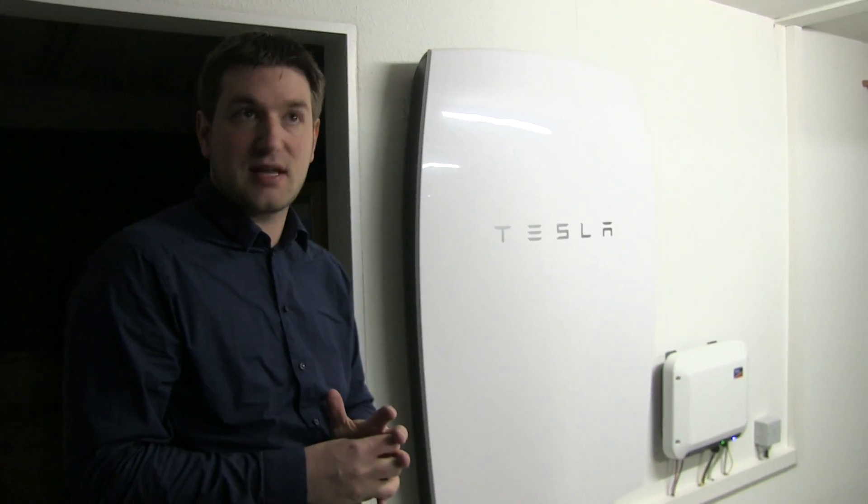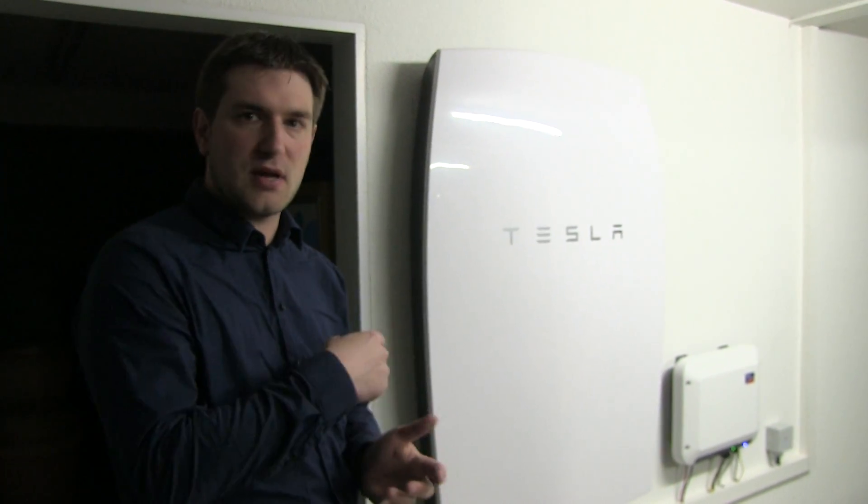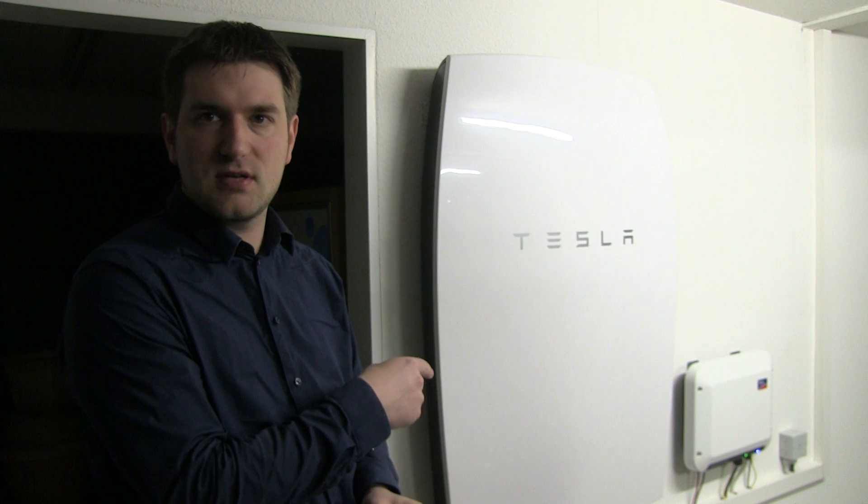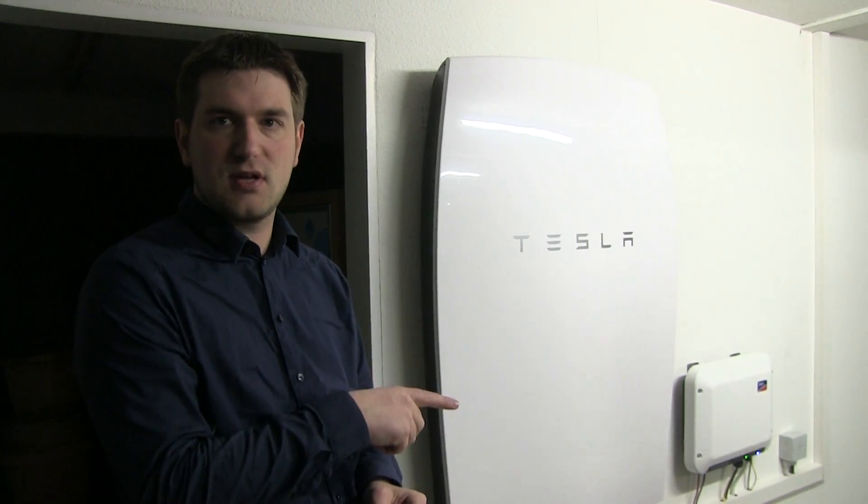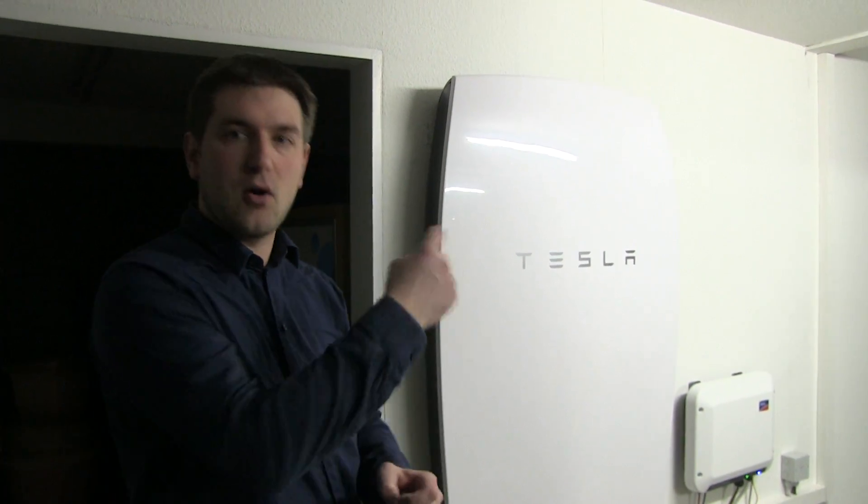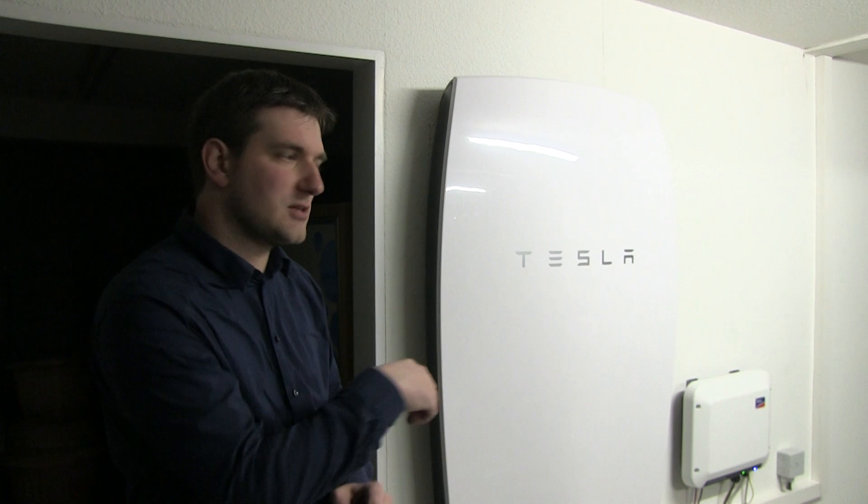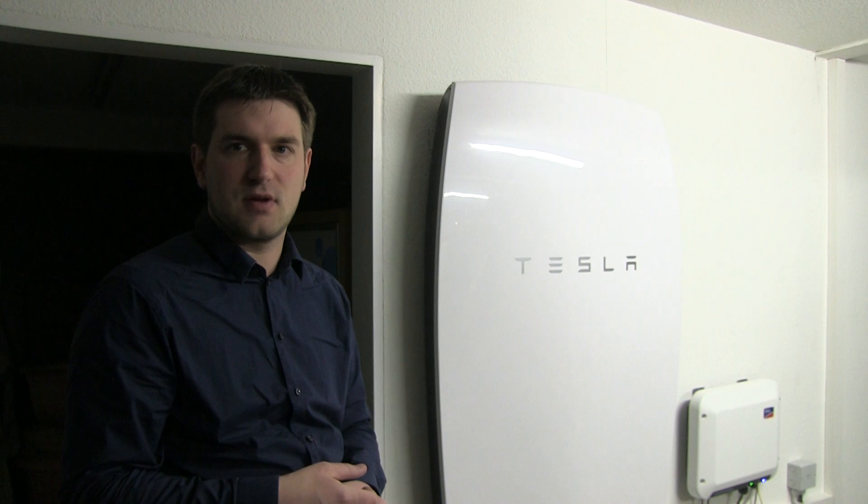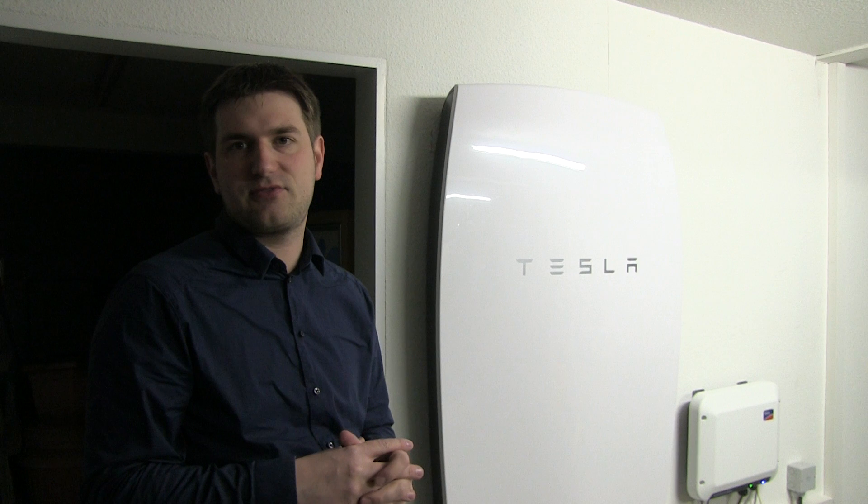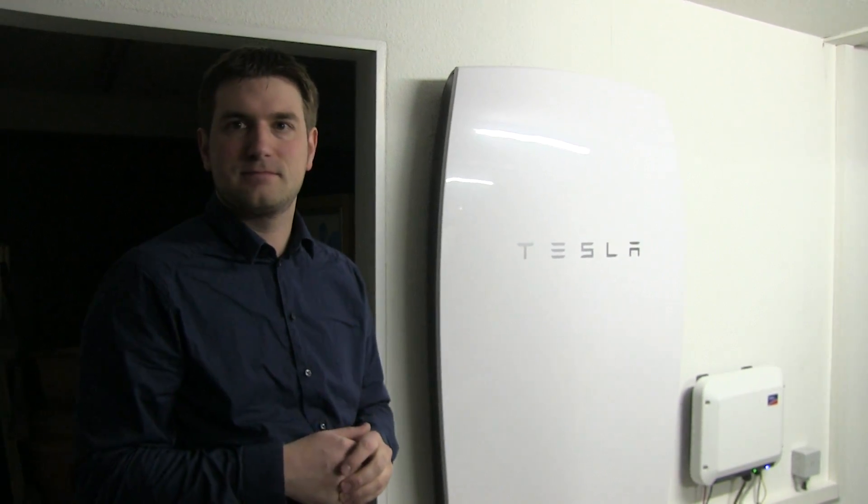And what is the difference between Powerwall 1 and 2? The most different is the capacity. The Powerwall 1 has 6.4 kilowatt hours. The Powerwall 2 will have 13.5 kilowatt hours. The power is different. I have 2.5 kilowatt input and output and the Powerwall 2 will have 5. But in the German regulations you're only allowed to use 4.6. Regulations, one phase, three phase, you don't have too much power on one phase.